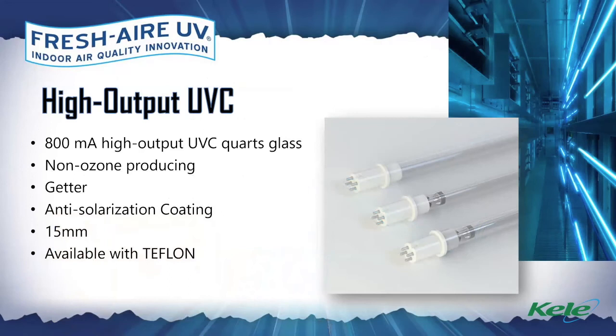Now, there's a lot of types of UV lamps, and it's nice to have an understanding of the kind of lamp. There's lamps called soft glass, which is a soda lime mineral, and then there's quartz glass, and we use quartz glass lamps in our UV systems. We have lamps that last 1 year and 2 years, and we even have lamps that have a special Teflon encapsulation. Should a lamp break, no glass or mercury could escape, and we would use that for sensitive applications like food production and things of that nature.